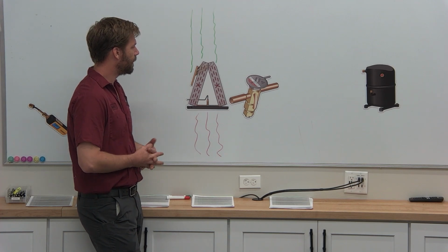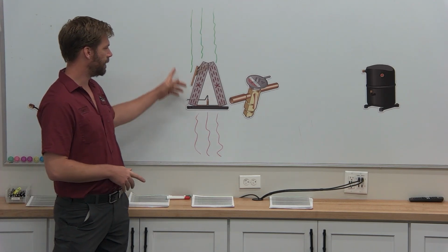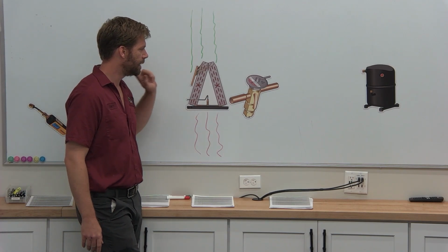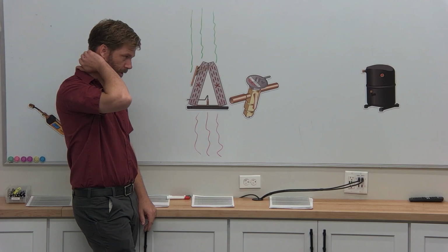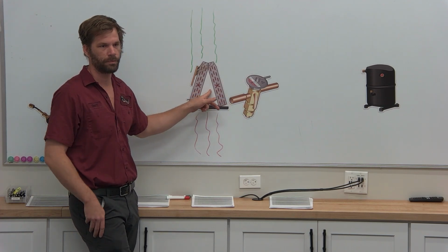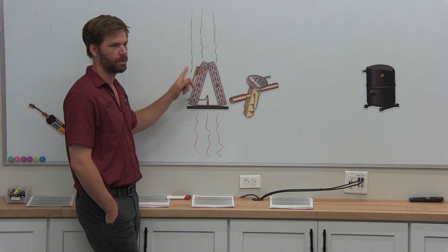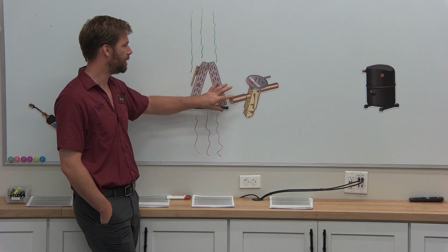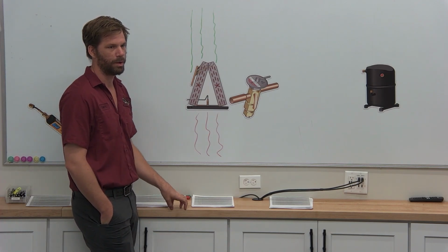But in no situation will you ever have a high temperature split, a 25-degree temperature split, because you have a failed TXV. Right? A failed TXV is restricting how much refrigerant is coming into this coil. So the issue that we're experiencing is a warm coil. We actually have less refrigerant than we need to keep this coil really cold.